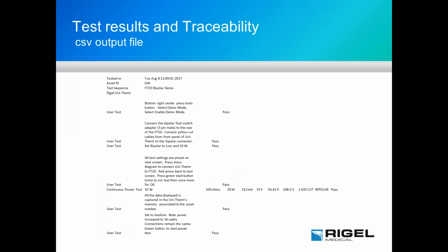I spoke a couple of times of doing a test in the auto sequence mode, and I just wanted to share with you what the output of that test would look like. So important aspects here is we have the test date and time. Everything is associated to an asset ID, which is entered into the Unitherm at the very beginning of a test. It shows what test sequence was chosen. In this case, it's just a small little demo test that we have available for the generator and the analyzer. You see the instructions that we provide, and then you also see when you go down two-thirds of the page down what the output results were.